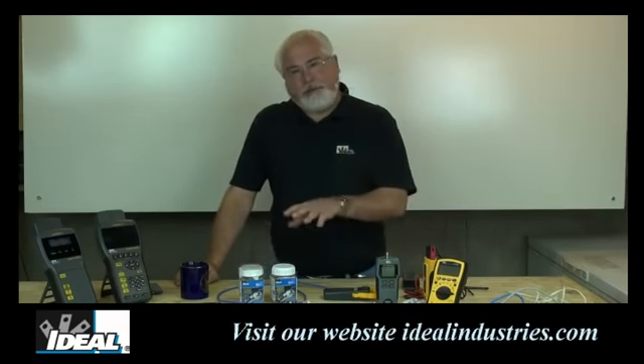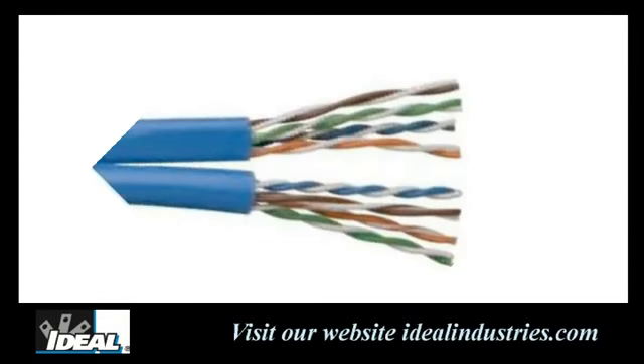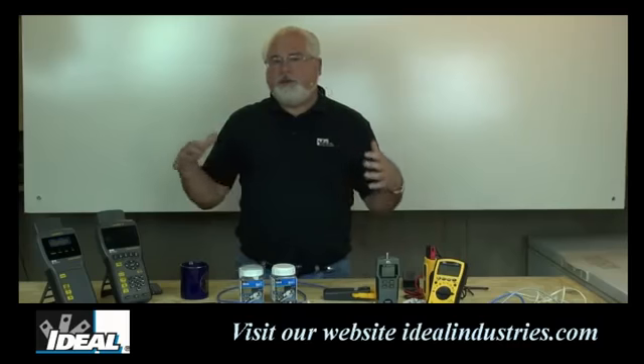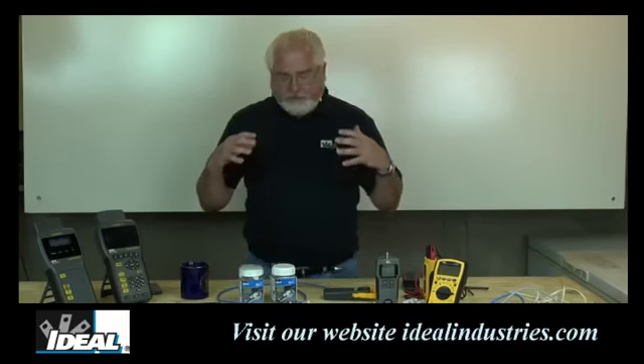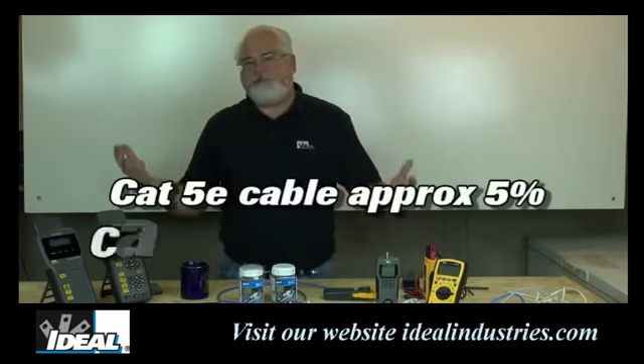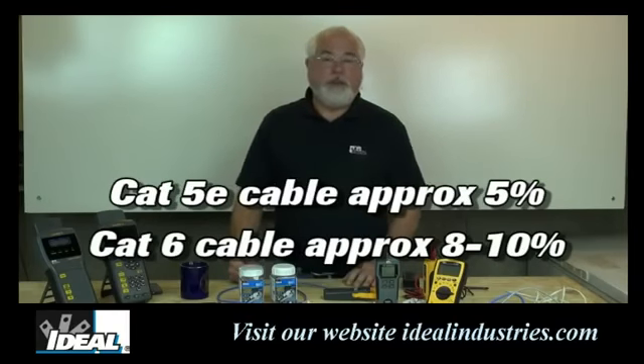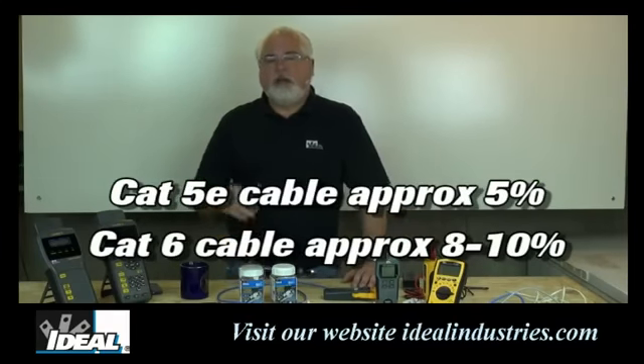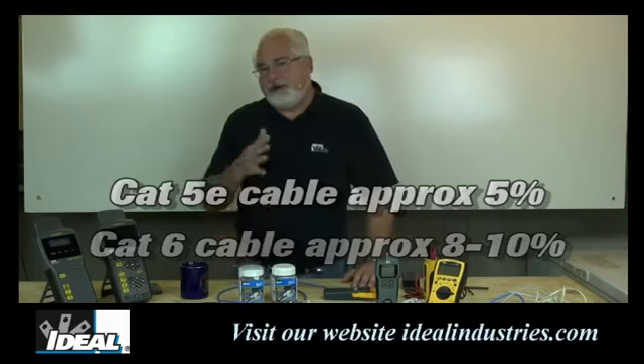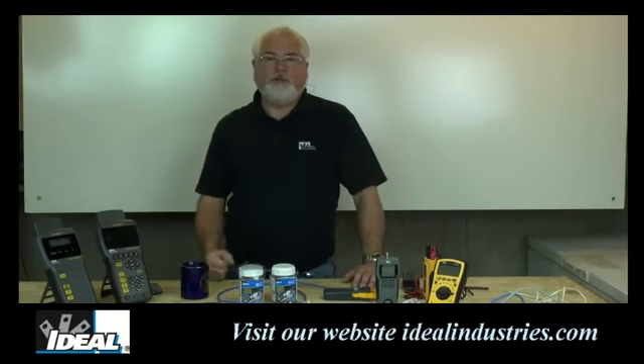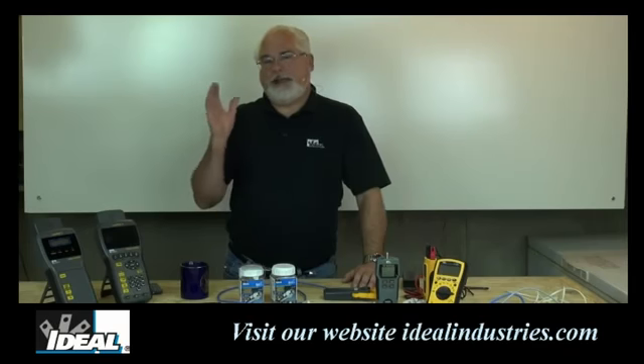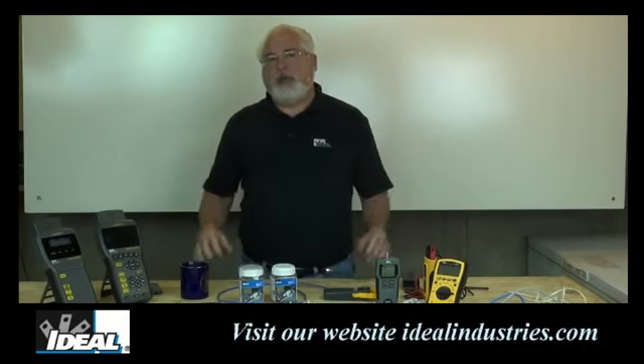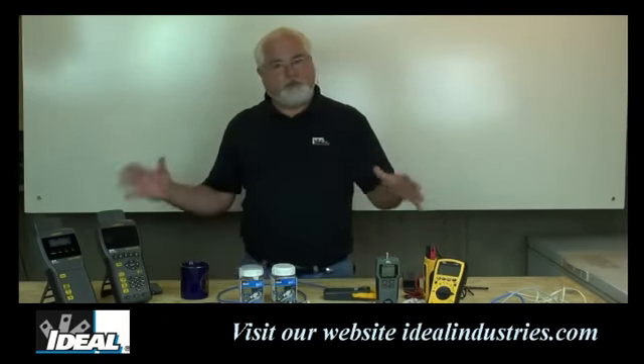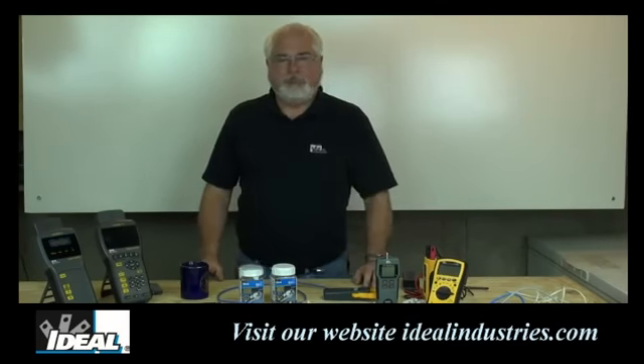Now, in category cable, we twist these pairs to eliminate noise or crosstalk, okay? And we twist each of the pairs at a different rate to, again, help eliminate noise and crosstalk. So we actually need to look at each one of these pairs. And in category 5E cable, I'm going to tell you it's roughly about 5%. So a 100-foot cable is maybe more like about 105 feet inside. Cat 6, it'll be in the 8 to 10% range, maybe roughly. It all depends on the amount of twisting you're doing in the pairs. And then Cat 6A, which is really, really twisted, it's going to be even worse than that. But as long as you stay under our 100-meter rule set by the industry, the system should be working, okay?